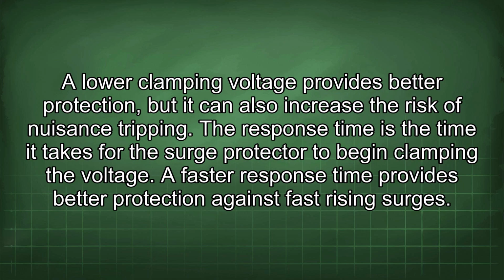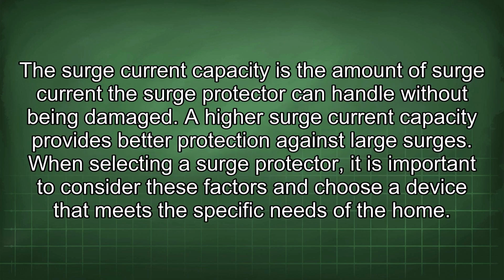A lower clamping voltage provides better protection, but it can also increase the risk of nuisance tripping. The response time is the time it takes for the surge protector to begin clamping the voltage. A faster response time provides better protection against fast rising surges. The surge current capacity is the amount of surge current the surge protector can handle without being damaged. A higher surge current capacity provides better protection against large surges.